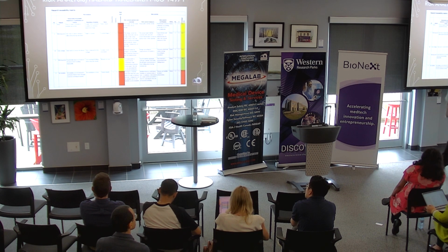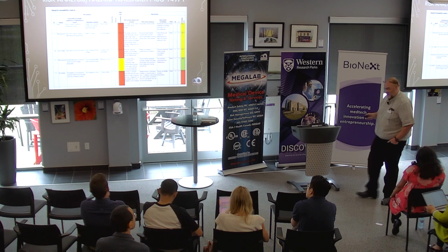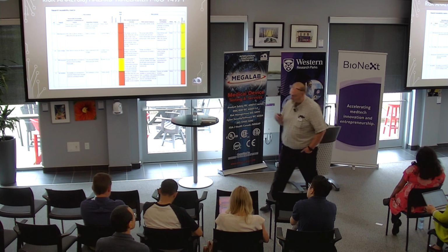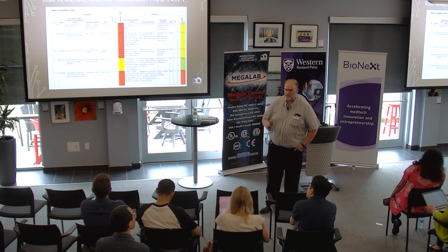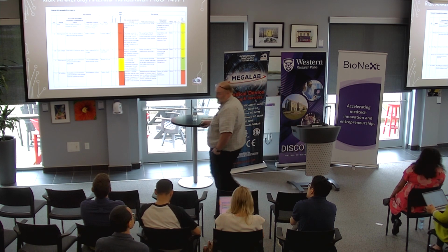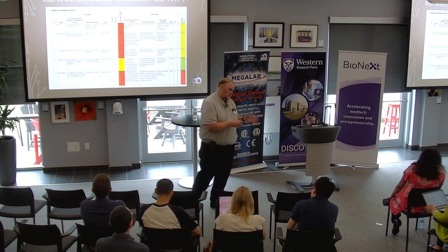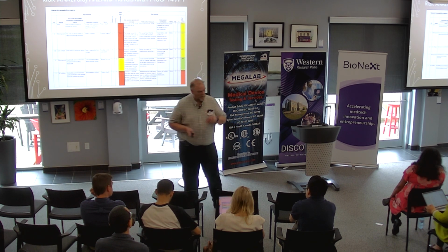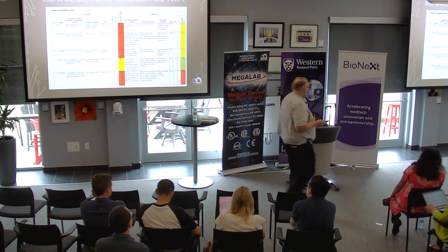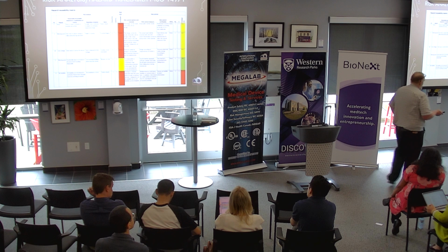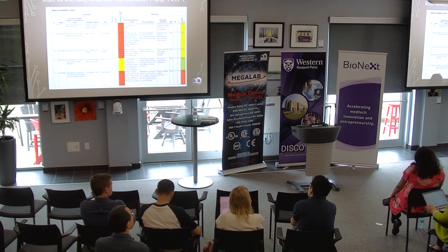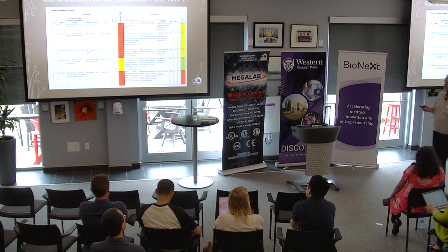Sort of associated with that in the medical device industry is hazard traceability. So you want to take that into consideration, but you also want to look at things like the severity of occurrences of things that might harm your patient. There's operator harm and then there's patient harm. So you have to split the two out and realize that there are situations where you might have a low occurrence, but it might be life-threatening. So you have to treat that as a high severity item. And then you can prioritize the design based on those functions as well.